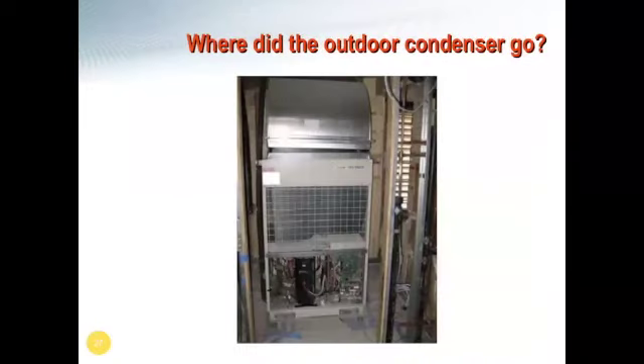One thing that I really do like to show is the installation of the condensing unit inside. This is one of the unique advantages of a VRF system. So this is actually in the Mitsubishi office over on 7th Ave. If you guys ever want to come see it, you are more than welcome to. This is the condensing unit that is serving the majority of the office space that I personally work in. We were able to install this unit inside, as is typical with a lot of applications. Basically, as long as you're introducing fresh air to the Mitsubishi condensing unit and ducting it out of the space, you're really able to put it almost anywhere within the building where you can spare a little bit of mechanical space, and that unit will act as if it is completely outside. It won't see any derating, it won't see any issues with performance.